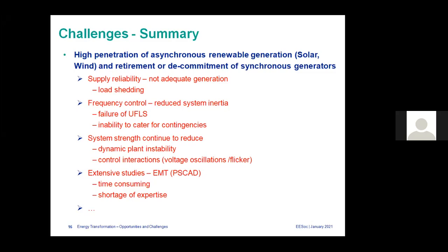So as we discussed earlier, there will be supply reliability issues or not adequate generation. That means you might end up load shedding. It has happened most of the summers here. Or at least you will have to ask industries to shut down, especially aluminum pot lines, which has about 300 megawatt pot lines. There are contracts with them to shut the plant down for a couple of hours without any serious issues for their production. So you shed load when there is not enough generation.